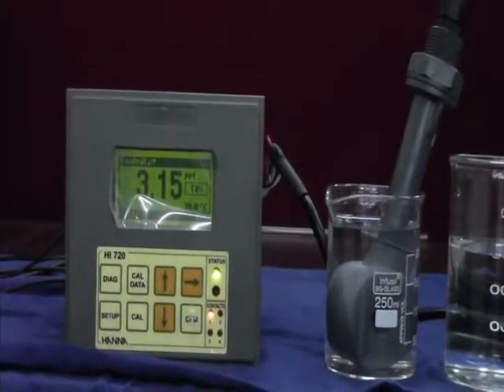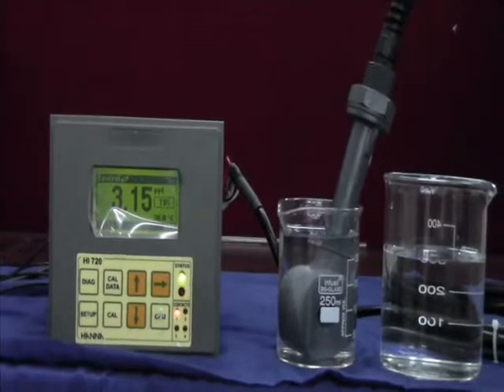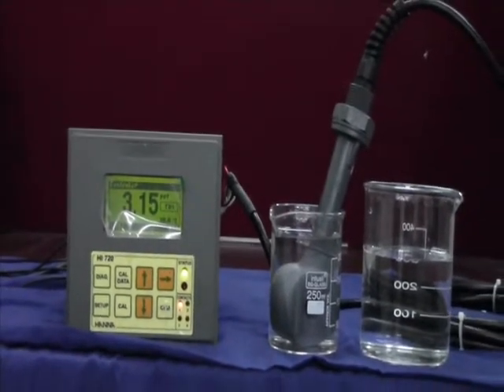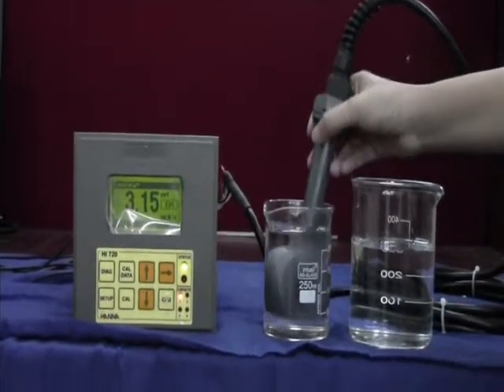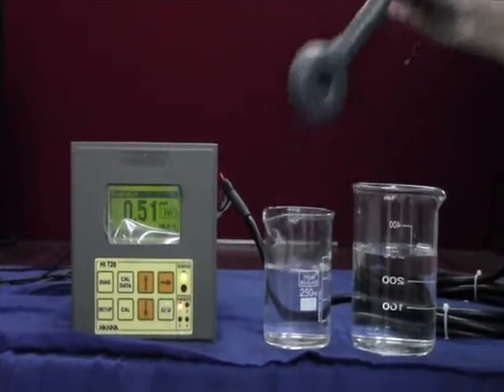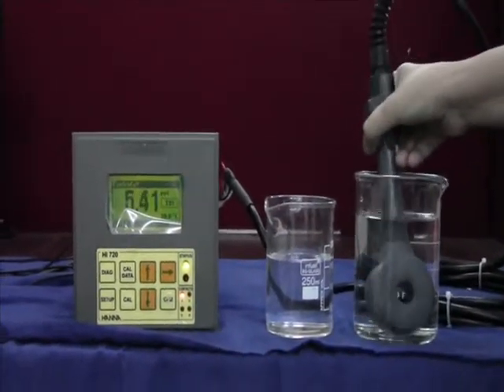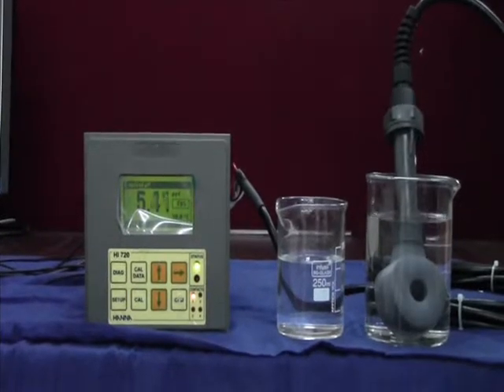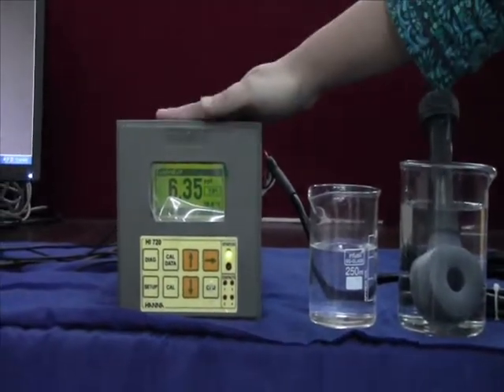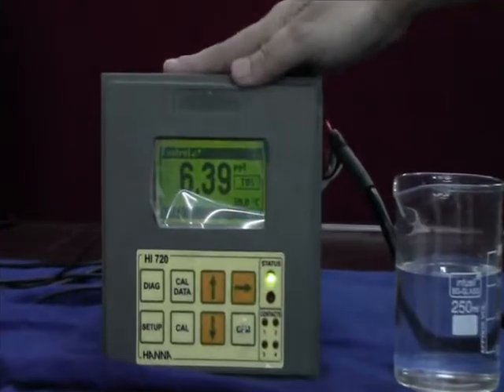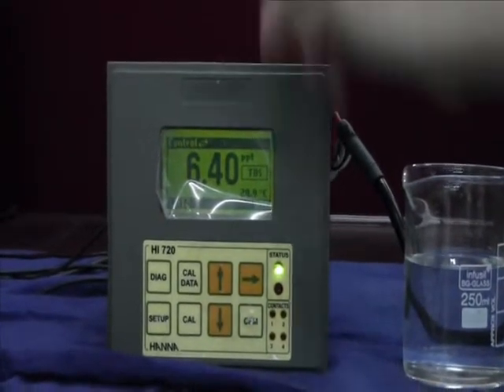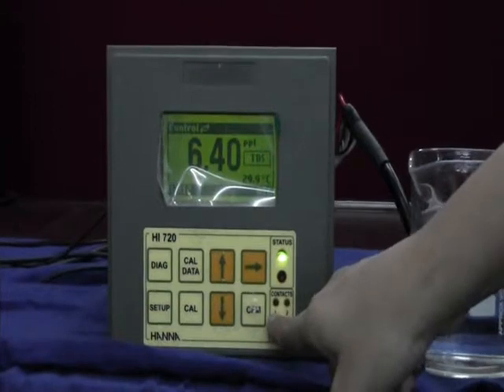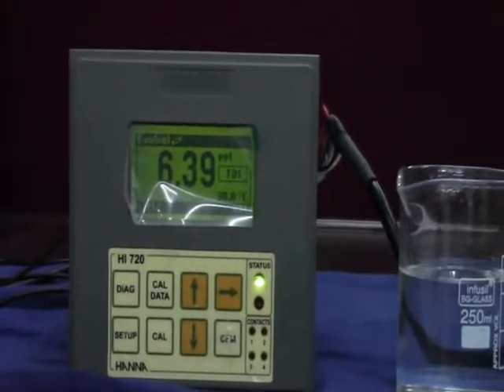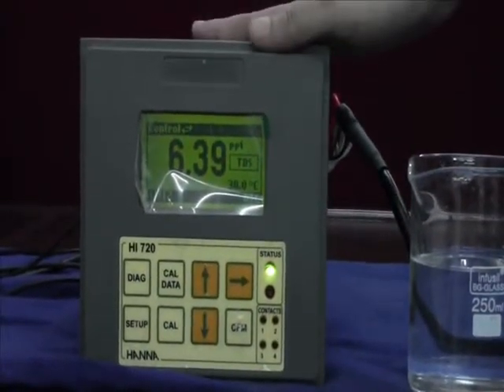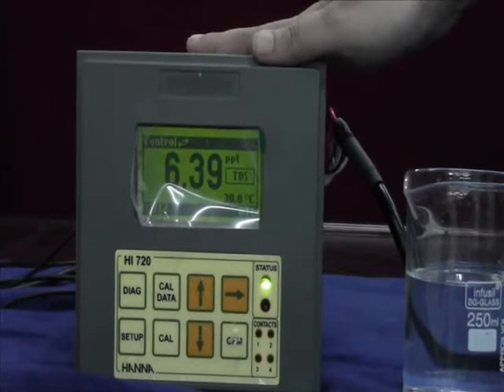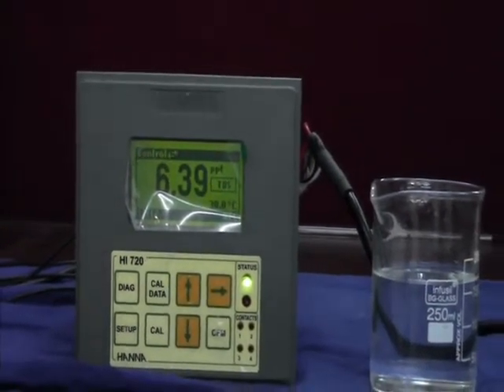Now the relay will turn off as soon as the readings cross the set point, which is set as 6 ppt. Now inserting the inductive probe in a sample with a higher ppt. The controller reads 6.39. The set point is 6 ppt. As you can see, the relay goes off. That is, a device which is connected to the controller will stop and the sample TDS will be controlled.